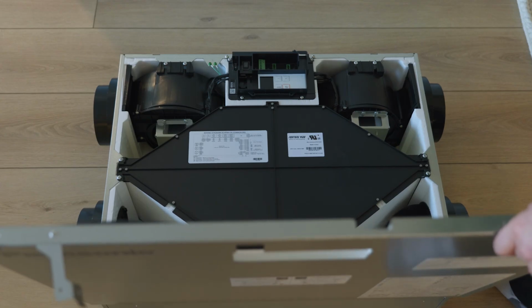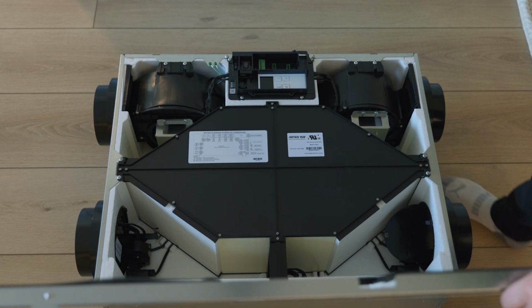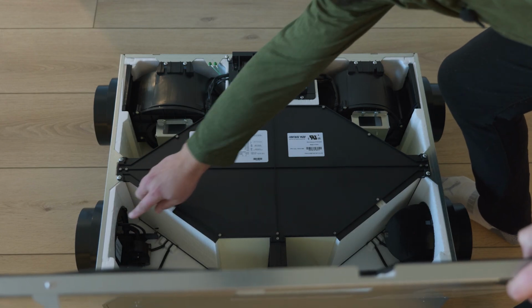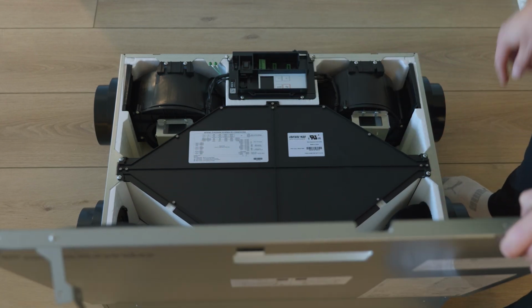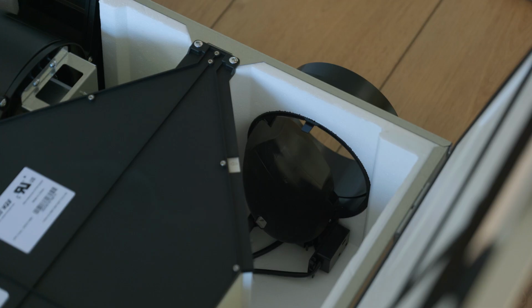One other important feature of an HRV or ERV is to have active dampers like seen here and here and here. Those dampers allow the unit to adjust and balance itself as well as to close down when not in use, so that we don't end up with an open pipe to the outside, reducing our energy efficiency.